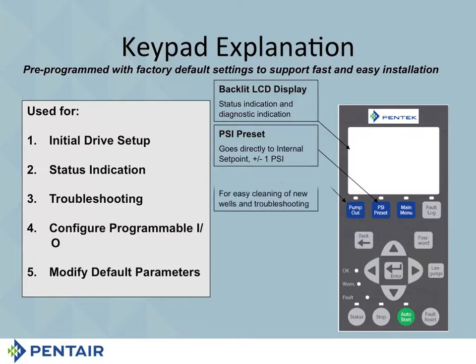There's also a blue button called pump out. Remember, you're putting single phase in, and if you want to, you can run a 3-phase motor. Now, it's really, really difficult to turn that 3-phase motor on if you don't have 3-phase power available to you. And of course, when you're cleaning out your well, you don't want this thing to stop. You want it to run. So you're not going to worry about pressure and everything. It's not going to stop if you push the pump out. Pump out overrides all of your pressure, and now it's just going to run this thing. So you decide how you want to run it.